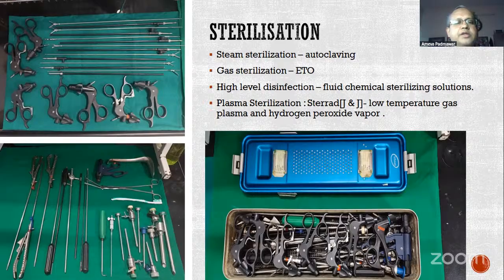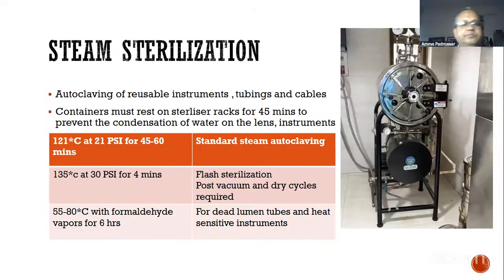And in the pictures, you can see that's how we lay our instruments out for drying. This is a standard set for any laparoscopy procedure. And then we pack them up in aluminum perforated containers to be assembled just before the next surgery. So the most important step is to autoclave these instruments. When it comes to choosing the autoclave, always choose a horizontal autoclave for your laparoscopy instruments, because the horizontal autoclave ensures that the instruments come out drier than the vertical ones. It is a useful tool available in every medical setup. Only for laparoscopy, you need the appropriate size.